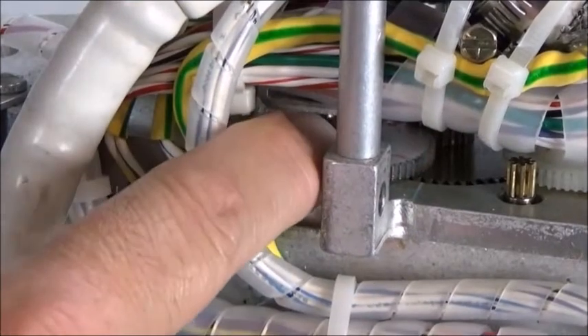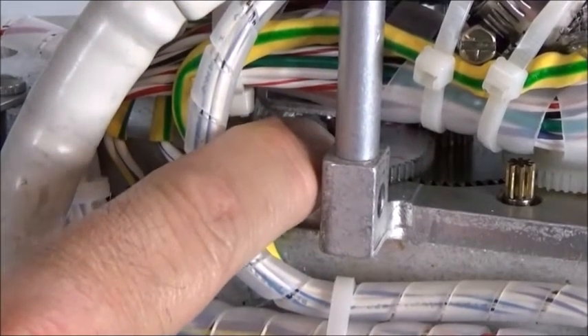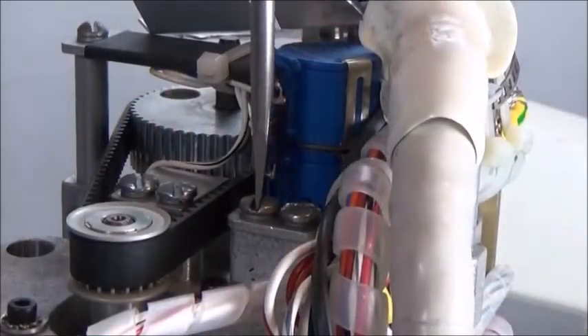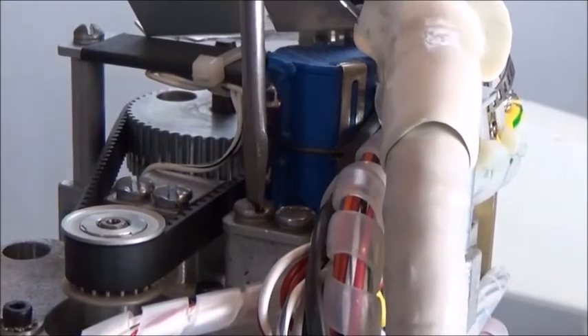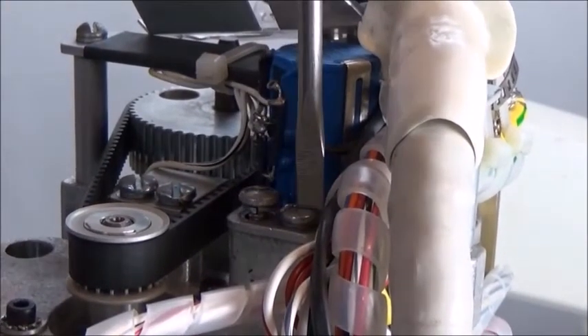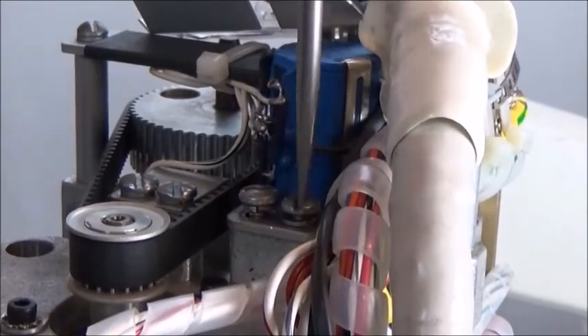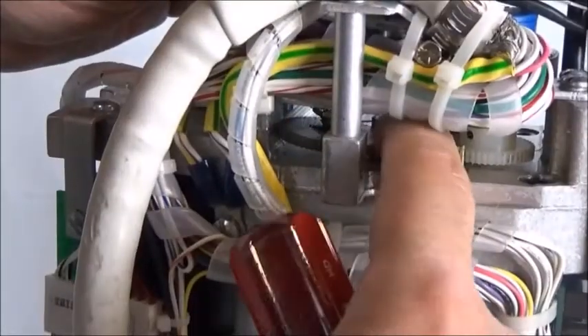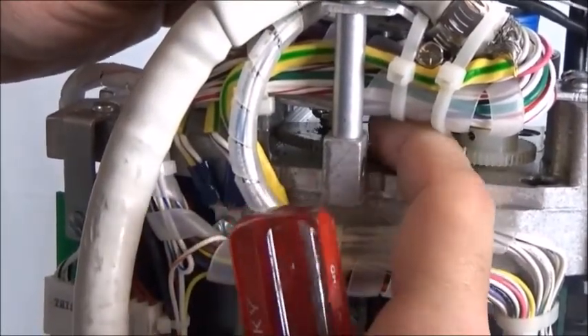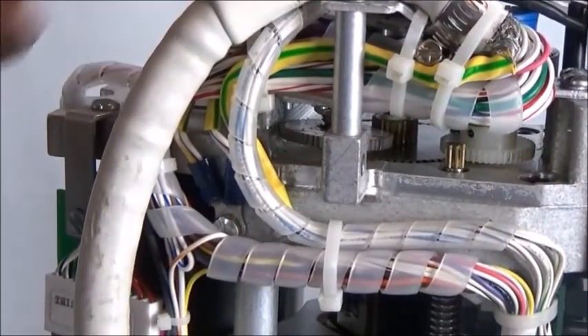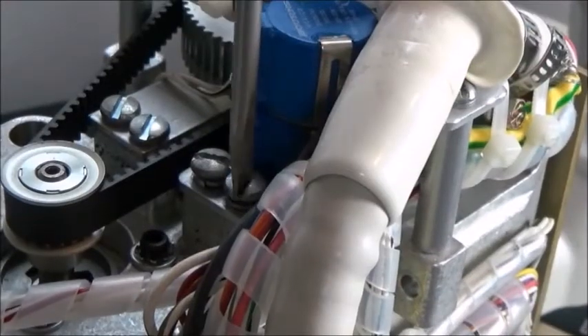If necessary, we will adjust the gear on R1 to get a proper reading. To do this, loosen the two screws holding R1 in place enough so that the R1 gear is no longer engaging the transfer gear it is attached to. Adjust the gear to get a reading of 0.23 to 0.25 volts DC on the display, then re-secure R1.